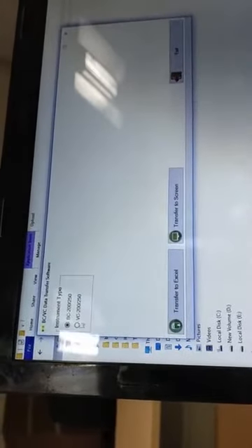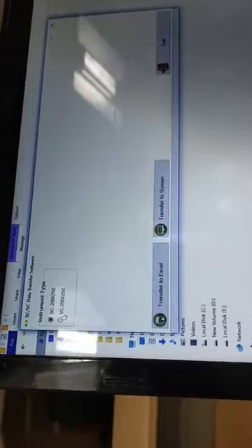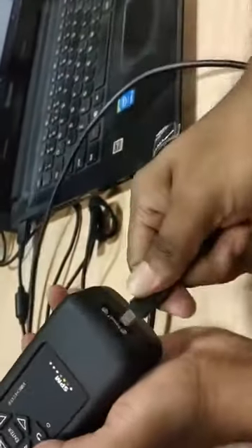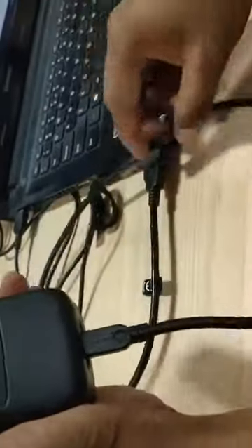After that, open this VC application. In this you have to select your instrument, meaning VC200. Here we are using VC200 instrument. VC means vibration checker. After that you have to connect this communication cable to PC and instrument, and switch on the instrument. After switching on the instrument, select the VC200 option and transfer to Excel file.